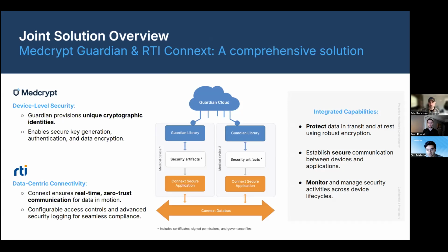Most medical devices are not like general IoT devices. They're in the market for years, like 5 to 7 years on average, and oftentimes run into complexities in actually updating them. So by improving the cybersecurity of the device and how data is transmitted and stored, as well as enabling things like secure updates, you're ensuring the lifecycle of the device is able to stay on market longer.